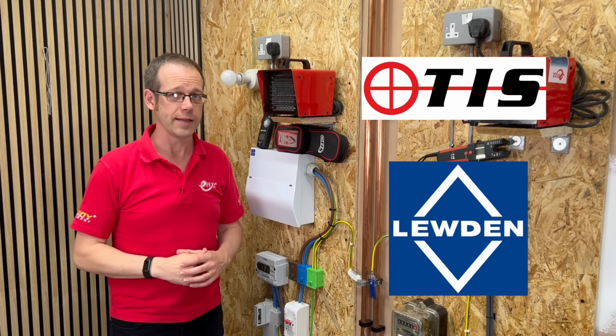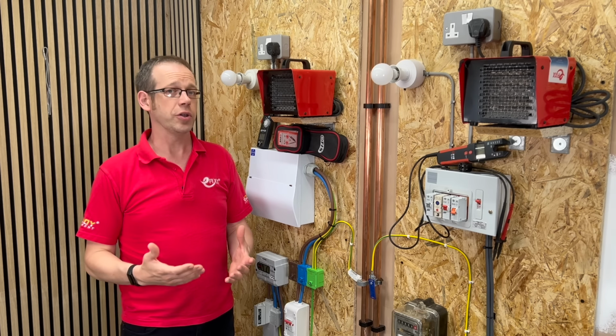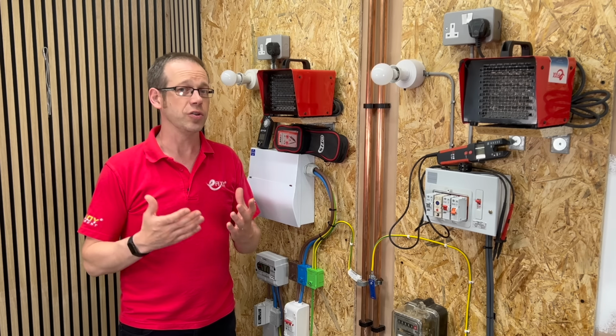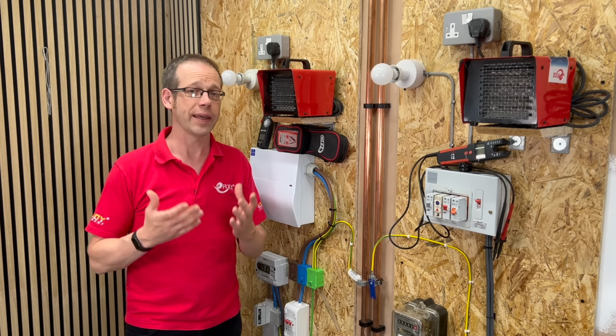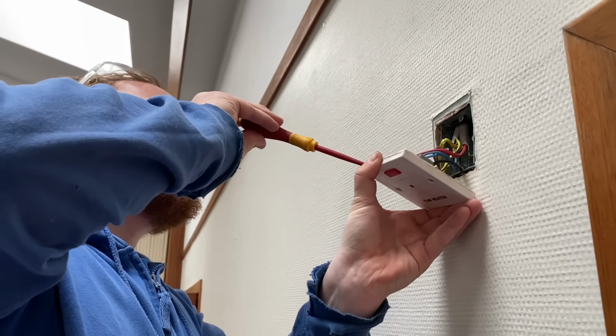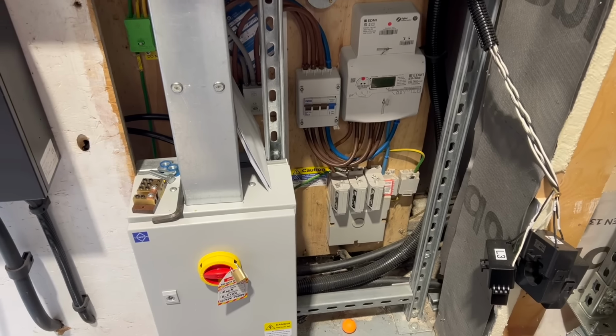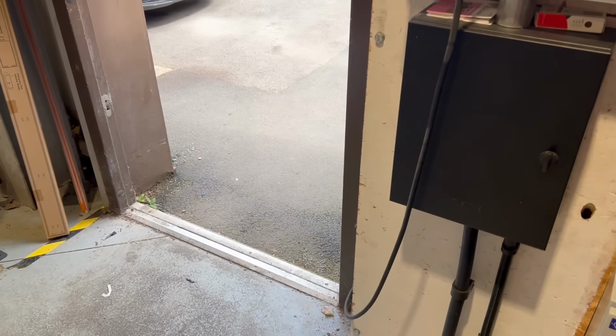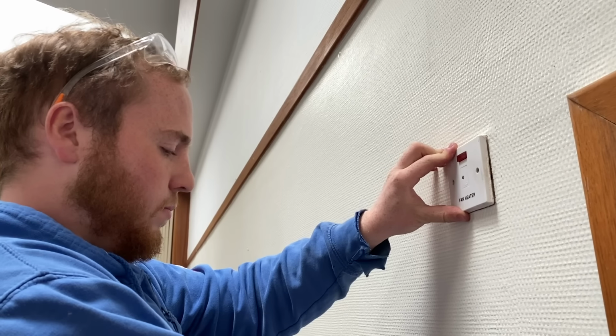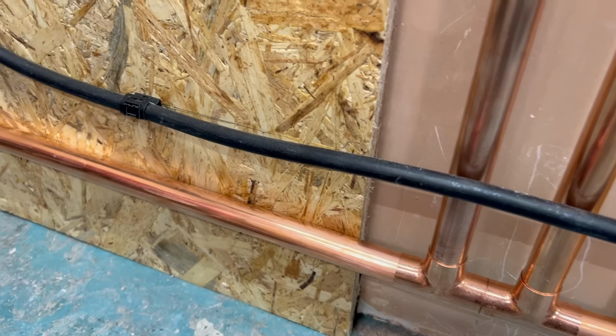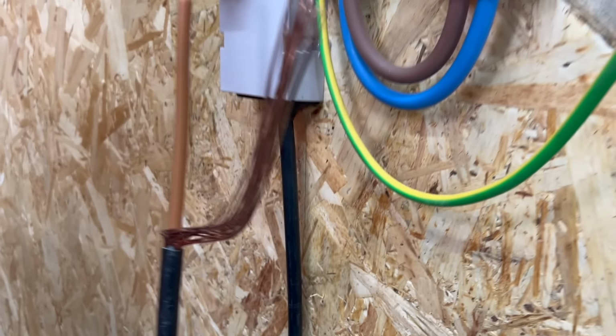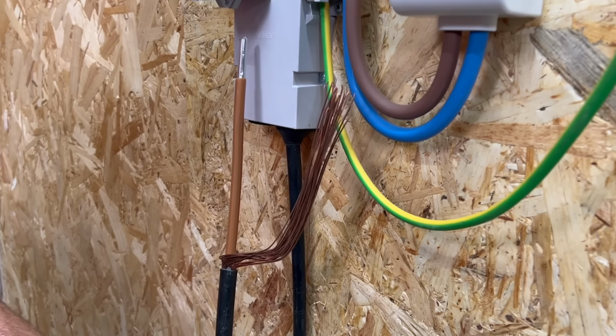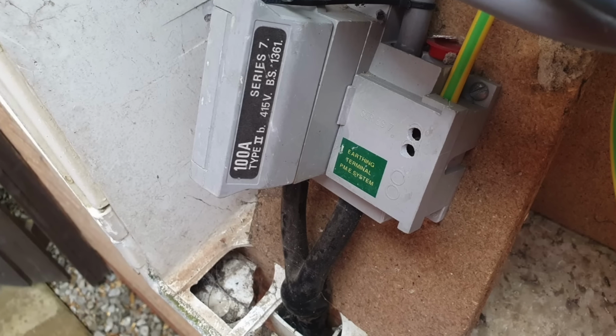It's the service head. First up, as we showed in our introduction, we've stumbled across the much discussed neutral current diversion that's becoming an increasing scourge to properties, people, and electricians. It occurs when there's a problem outside your property, and it's also outside the control of you, the electrician, or the property owner. The vast majority of properties in the UK are now connected to the distribution network via cables that have a combined neutral and earth conductor into the property, giving us a TNCS supply.